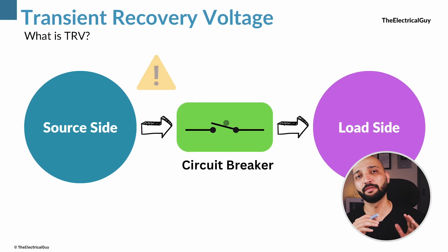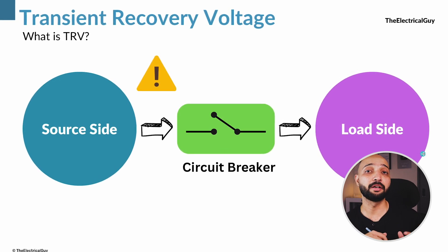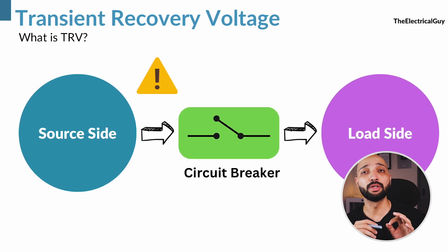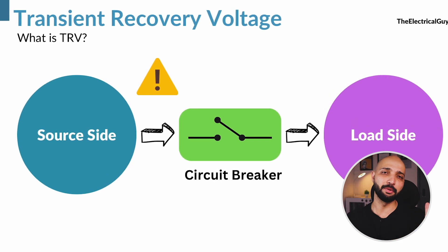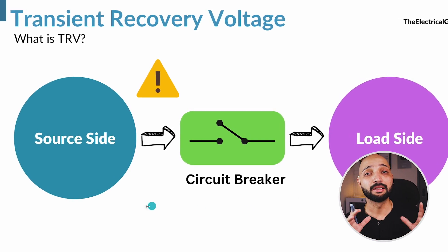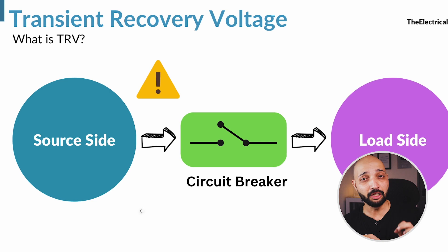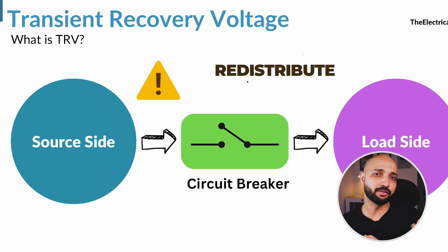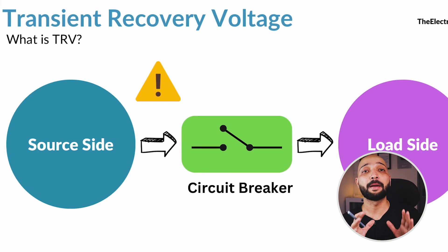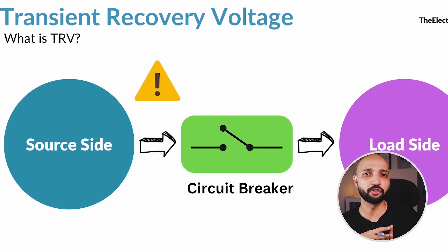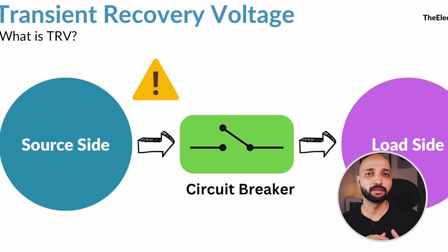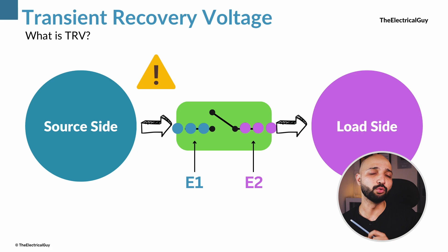Now, if there is a fault and the circuit breaker opens, these two networks will be disconnected from each other. Since the link between the two networks is broken, the trapped charges in each network will try to redistribute. As a result, each network develops a voltage that appears simultaneously across the respective terminals of the interrupter, labeled as E1 and E2, as you can see on the screen.